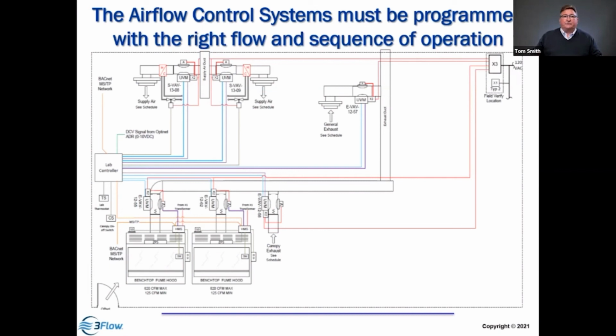And oftentimes we provide a diagram that looks like this. We've got our two hoods, and we notice a lot of instrumentation equipment for the hood. There's a hood monitor, a sash sensor, maybe a blue wall sensor. That's connected to a controller, or that actuates a valve. But it's also connected to the general exhaust and the air supply valves. So my question is, what's happening here?